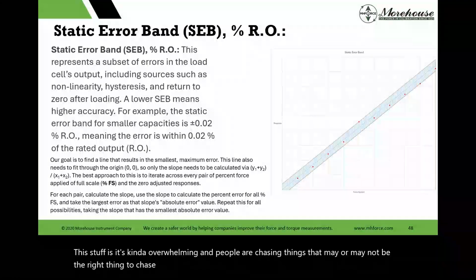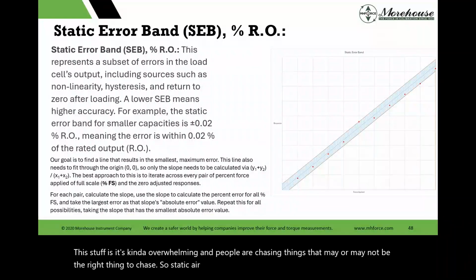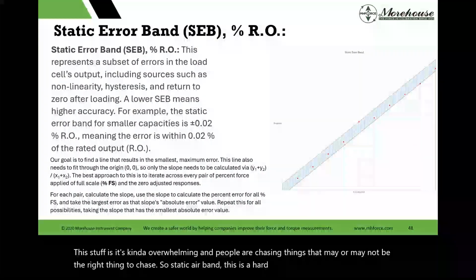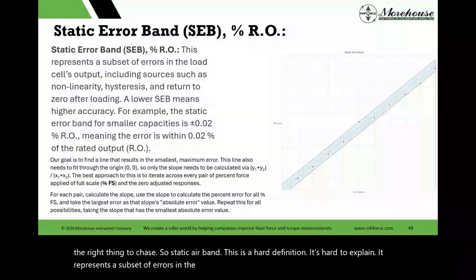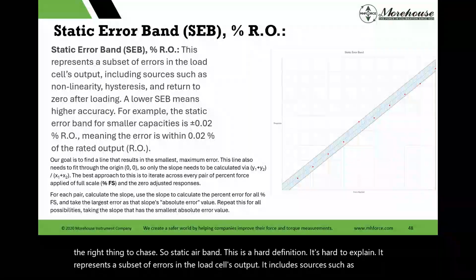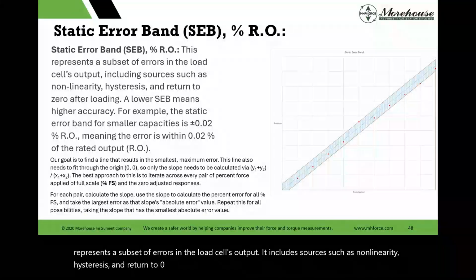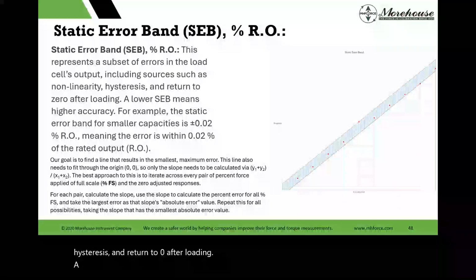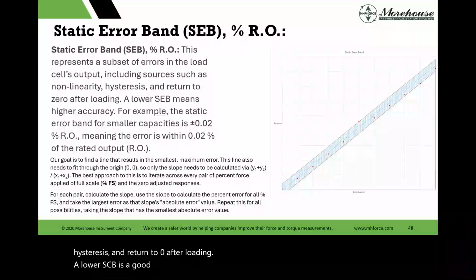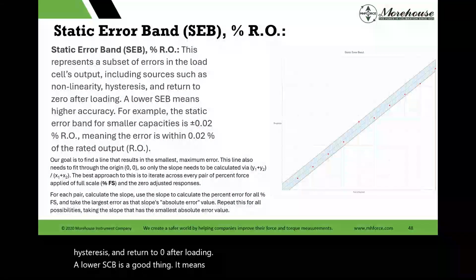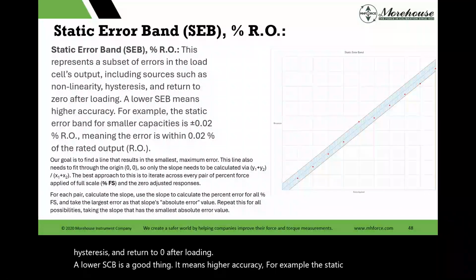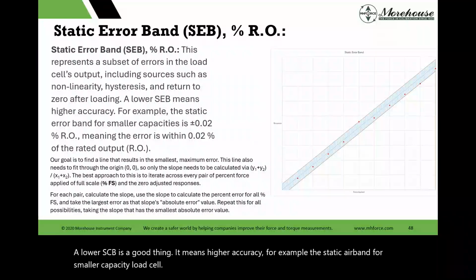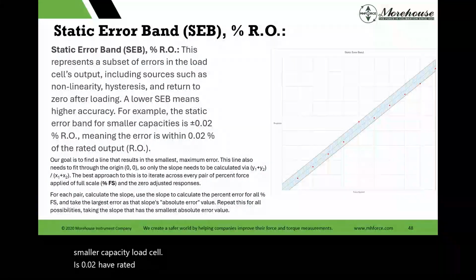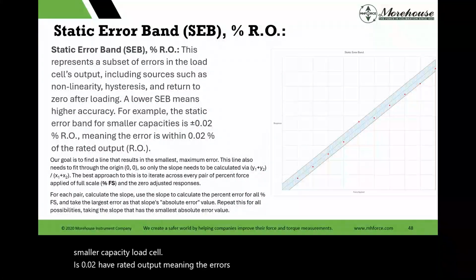So static error band, this is a hard definition. It's hard to explain. It represents a subset of errors in the load cell's output. It includes sources such as nonlinearity, hysteresis, and return to 0 after loading. A lower SEB is a good thing. It means higher accuracy. For example, the static error band for a smaller capacity load cell is 0.02 of rated output, meaning the error is within 0.02 of rated output.